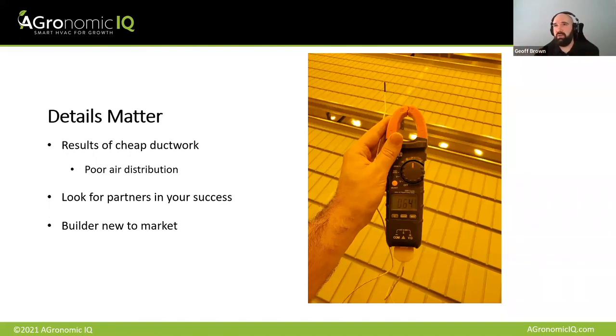Again, that's one of those things that we see all the time: growers are very good at creating horizontal air curtains in their room. They've got a bunch of air rotation fans pointing sideways, high supply, high return, and then wonder why no air gets down low. Well, you've all walked into a Costco or a Target and had the fans blow on you. It's literally creating an air curtain. It's designed to block mixing between inside and outside. And if you do that with your air rotation fans, you're going to accomplish exactly the same thing. So intelligently applied air distribution is really, really important.